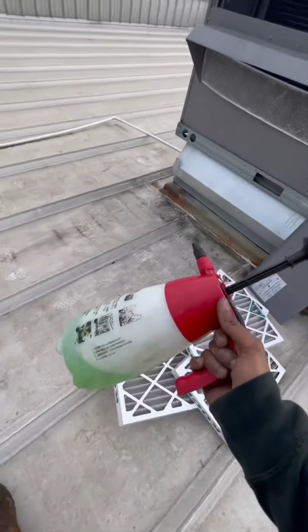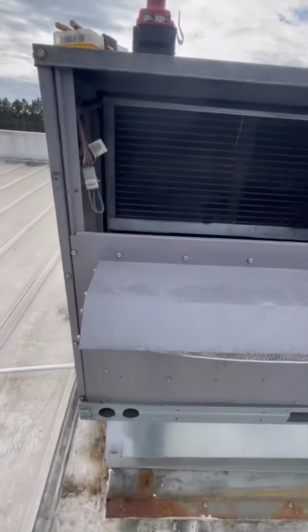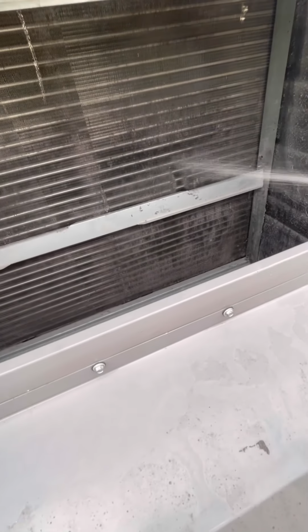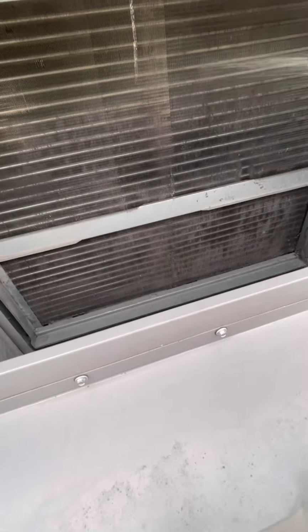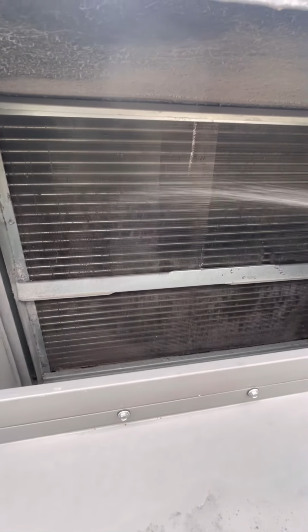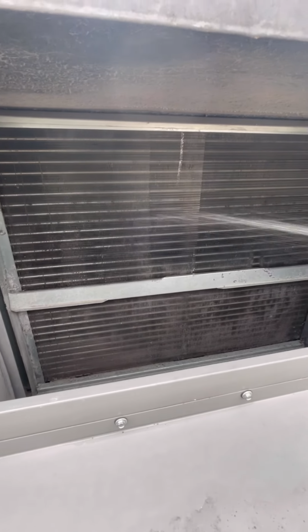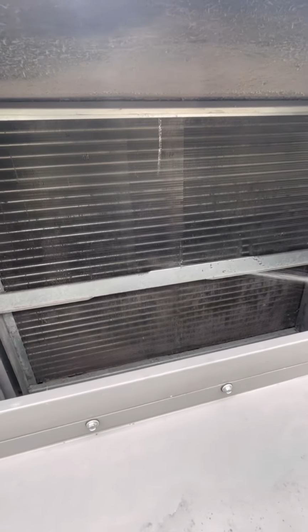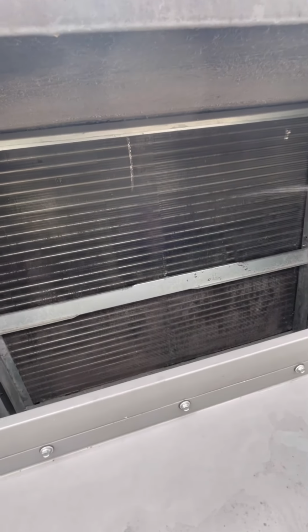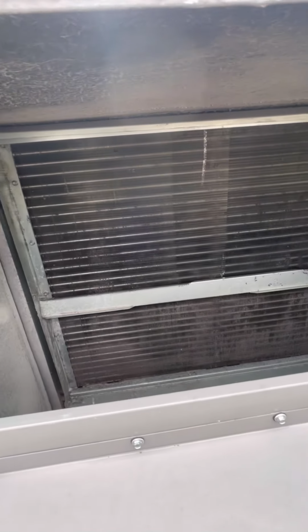And these are our 4 old filters. So we got our green evaporator coil cleaner, and we just give this a good spray down of the coils. Nothing too crazy, you don't gotta overdo it, but you wanna make sure it gets nice and clean. Just give it a good spray down, that way things are working how they should be.